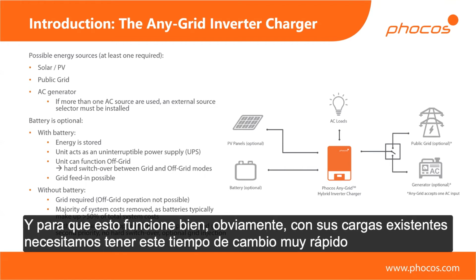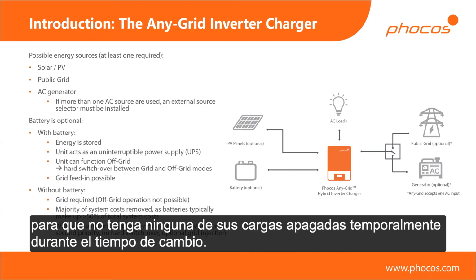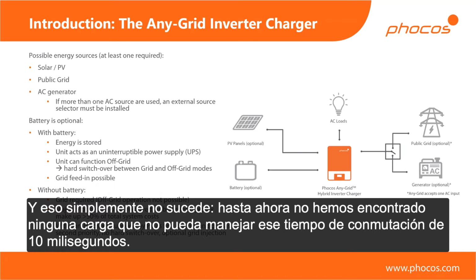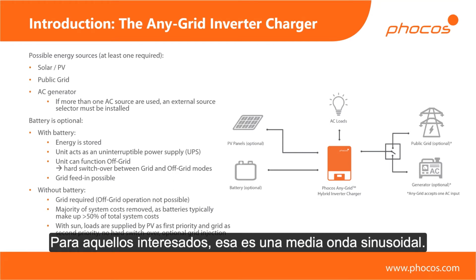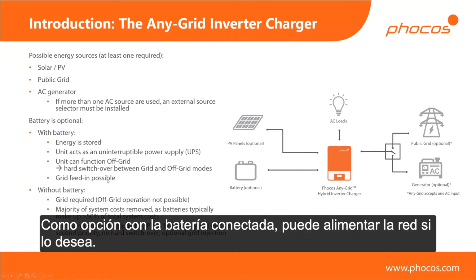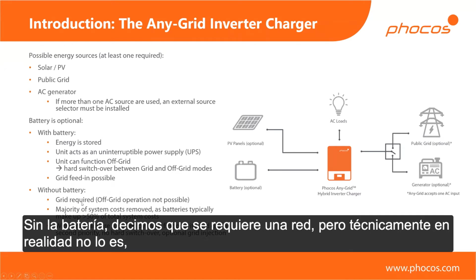For this to work well with your existing loads, we need a very quick switch-over time, so that none of your loads temporarily turn off during the switch-over. We haven't met any loads so far that will not handle that 10 millisecond switch-over time. For those interested, that's half a sine wave. And as an option, with a connected battery, you can feed into the grid if you like. Without the battery, we say that a grid is required. Technically speaking, it's actually not.